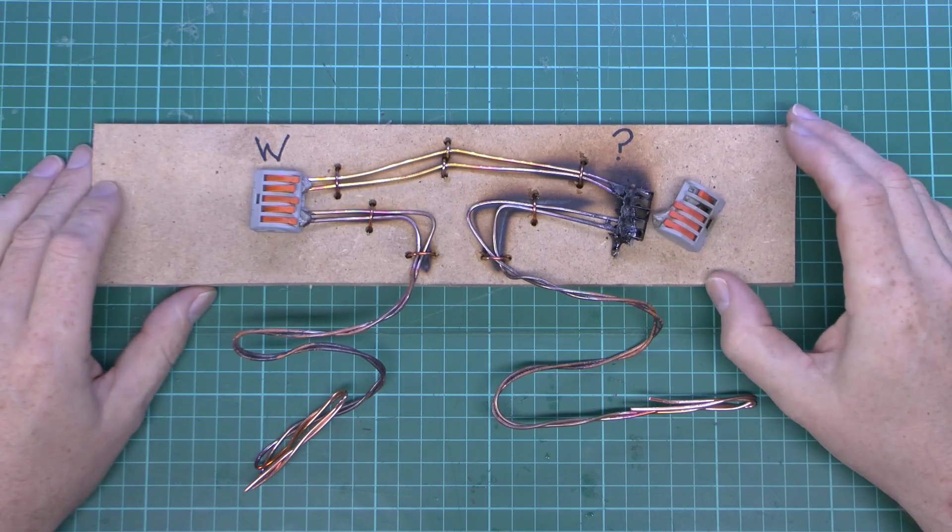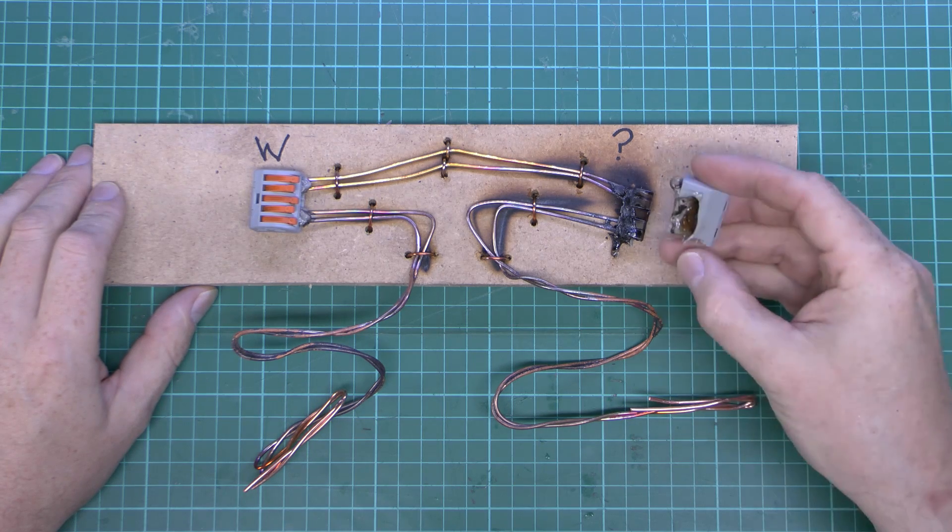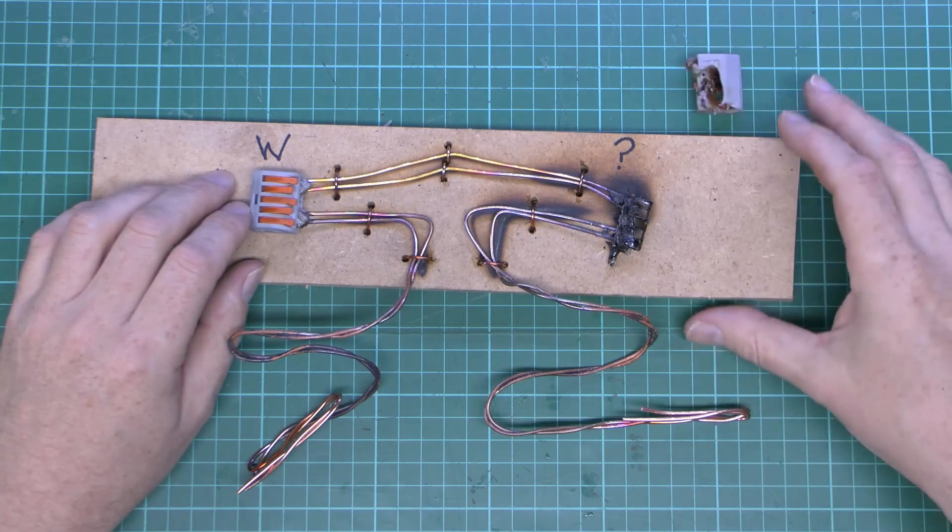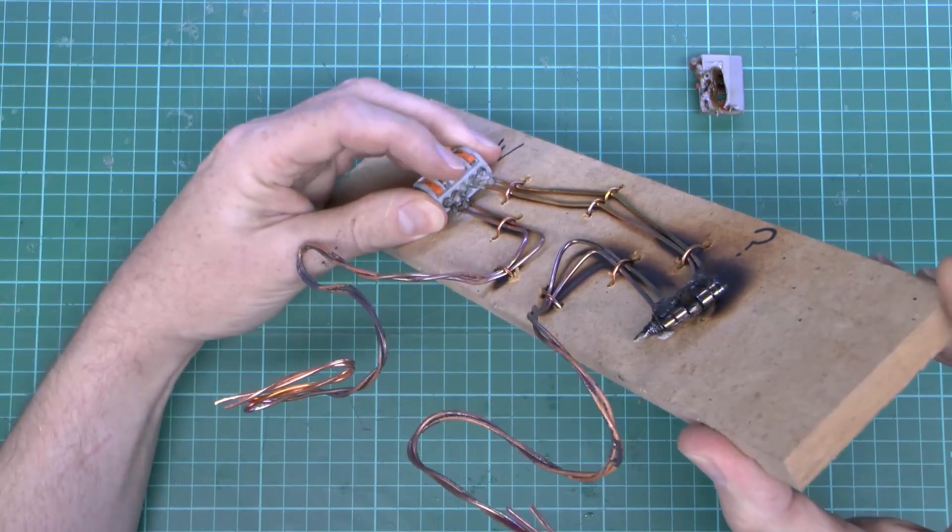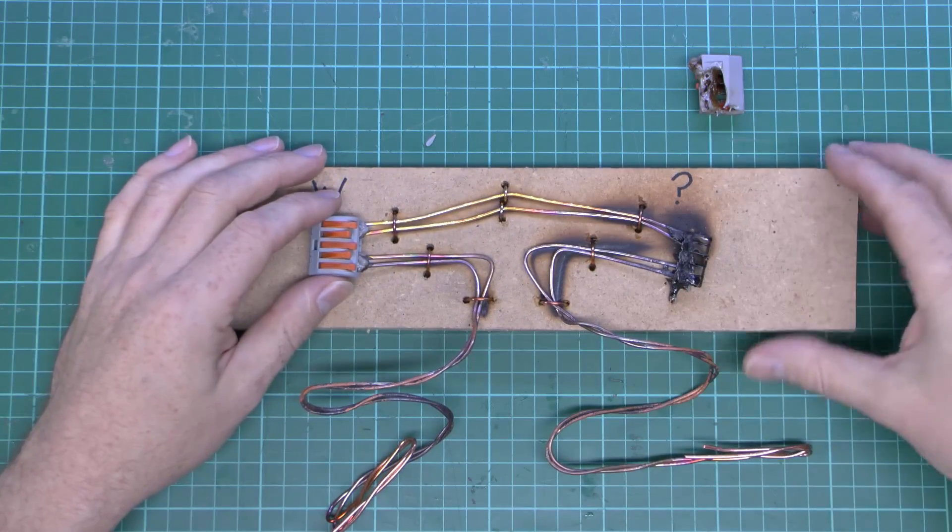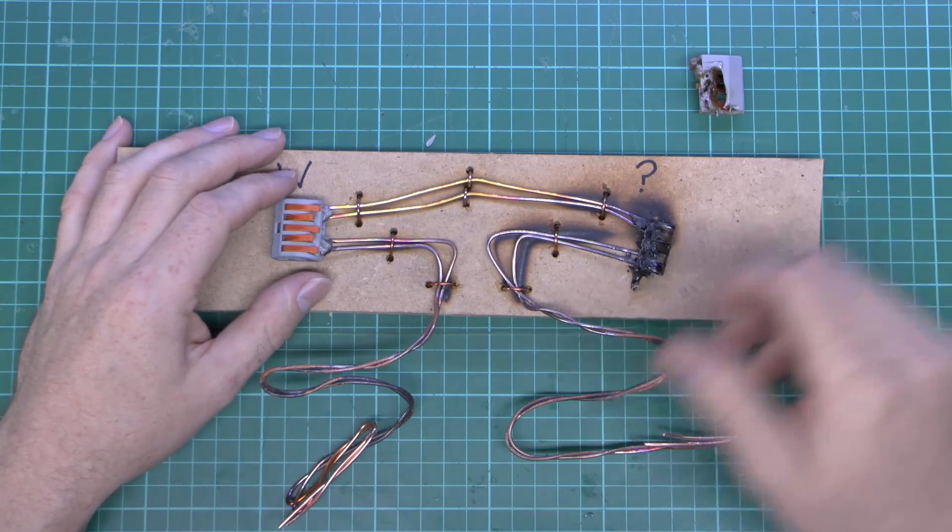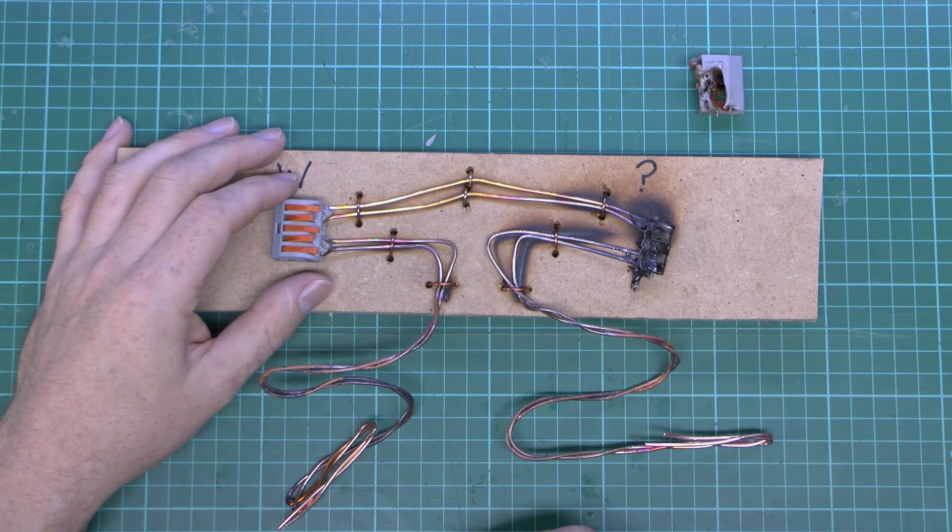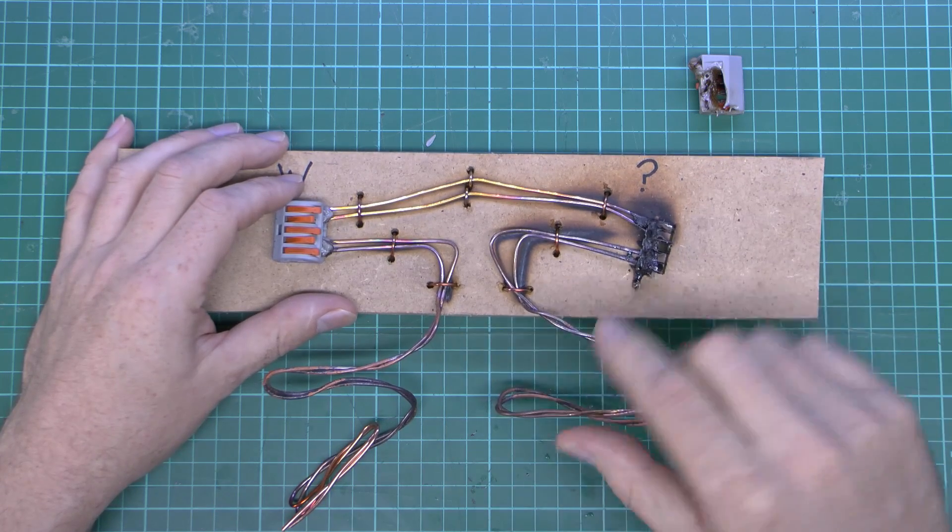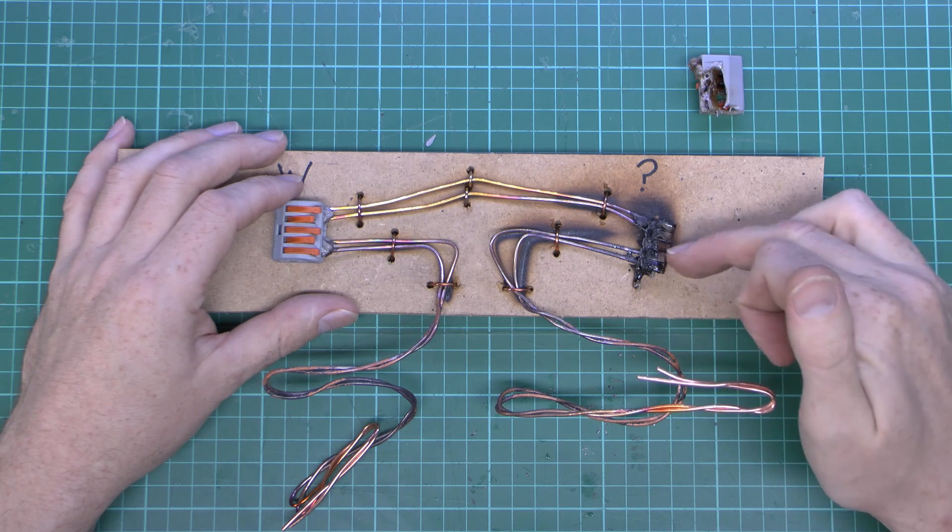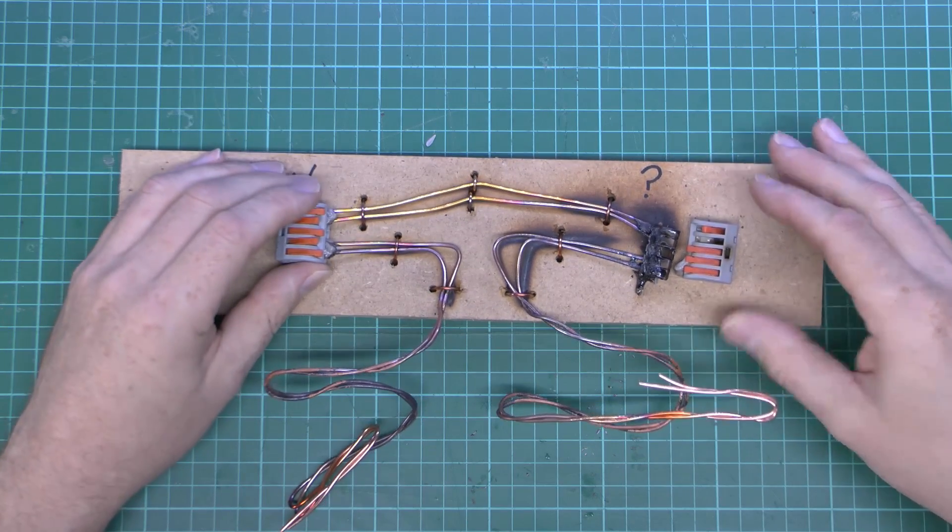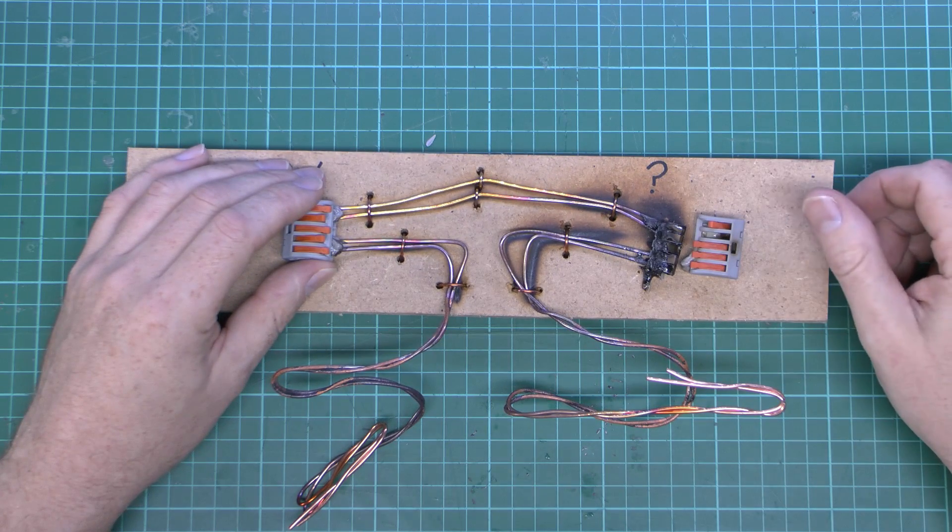Now this is what's left after the wreckage there, and this is the FACO connector, and as you can see it has melted completely off of the terminals, although the terminals are still intact, the two wires are still in there. The WAGO one has fared slightly better, but of course it has still melted significantly, so it's completely unusable and destroyed, so although it's better it's certainly not damage-free. Bearing in mind though, this was at 150-odd amps, five times or more than the things are actually rated for, and you can see the copper wire has gone various different shades due to the reaction with the oxygen in the air. And so this is 2.5 mm², so we have two of those, and it was a total of 5 mm² wire actually feeding both of those, and did that so the weak point was obviously the connectors themselves. So yes, that one is slightly worse, but not by much, and this one obviously melted, and bearing in mind we had to get to ridiculously high currents before we saw any kind of melting or overheating there.